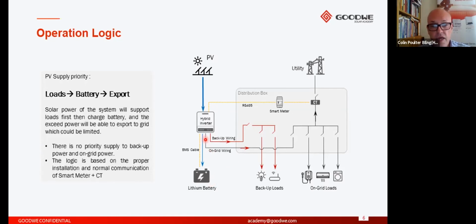Here on the output side, we have our on-grid connection, which is the way you'd connect a standard inverter to supply energy to support the loads of the building. But in red, you can see we also have a dedicated AC output for any essential circuits. There's a separation between these two circuits, and the backup side will in no way be connected to the on-grid side.